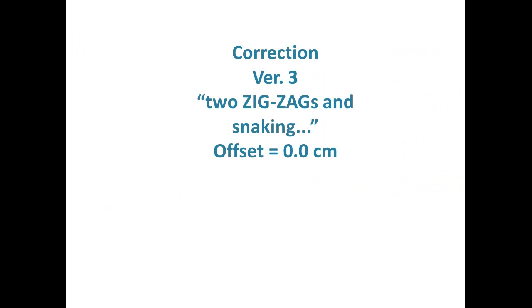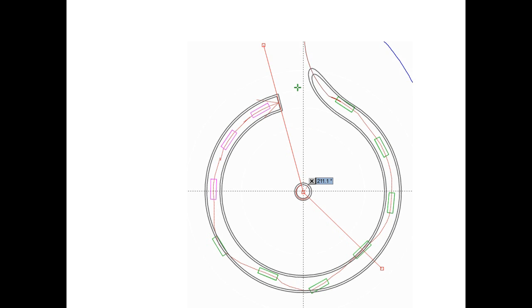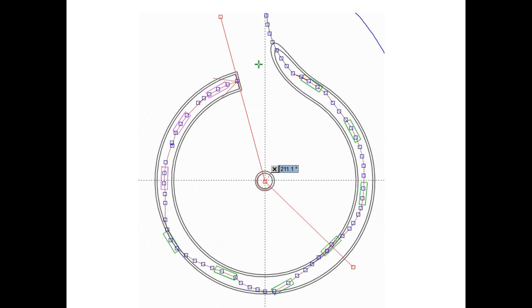And the last correction method we are discussing here is to construct such a shape of the source travel path that gives us a perfect fit with all points in the film angular measurement data. In this case the total error factor will be 0. We transform the points of the library applicator by introducing two zigzags and moving source path points away from or closer to the ring center. Here you can see the snaking result, where the source traveling line remains its location inside the applicator tube. Now all source positions precisely fit the source locations measured on film, and in principle we can create an applicator template of such snaking shape and save it for clinical use. But we think it is not practically necessary, because the snaking nature of the source cable is not predictable and depends on the source guide tube shape, and that is why we should use some average library model.